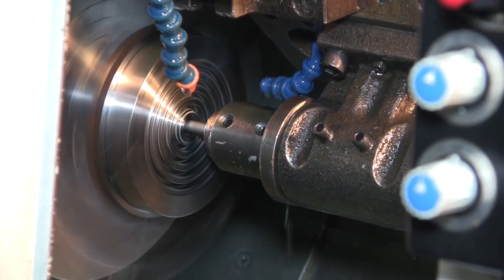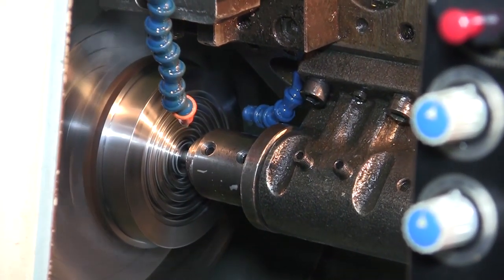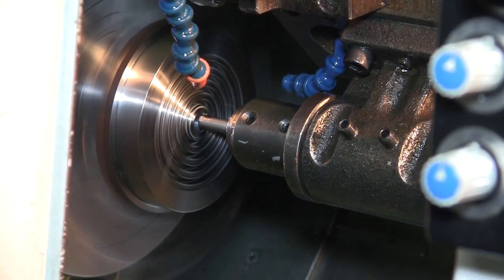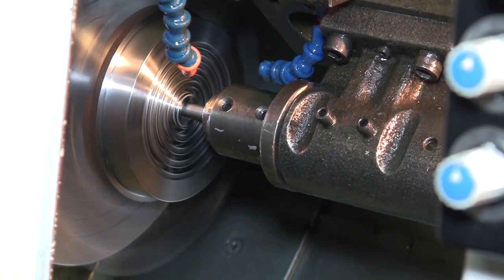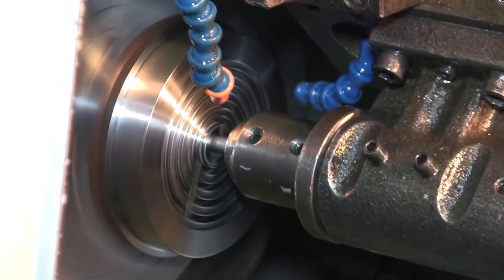This was the machine you used to have a FANUC 6 control on it, and I remember we had lots of troubles with the spindle drive and the control just not wanting to keep up to what you want to run with it. Yeah, it was just worn out. There wasn't much we could do with it — replacing the spindle drive and drive motors, the axis motors.